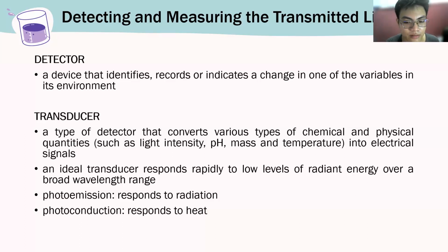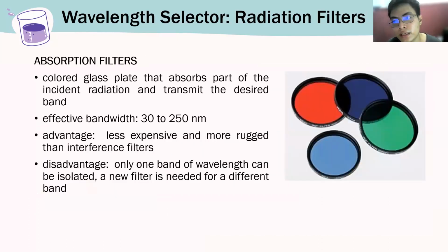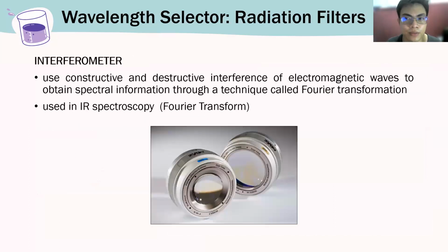So the grating helps us select the wavelength that's more appropriate in doing the measurement. Gumagamit tayo ng interference filter para yung undesired light ay ma-cancel out sa instrument. Okay? Kapag yan ay UV-vis, ito yung ginagamit na filter. Ayan, absorption filter. Okay? Pero kapag yan ay IR, ginagamit ay interferometer, which cancels out the IR from the surroundings.